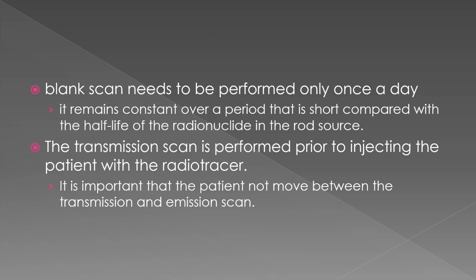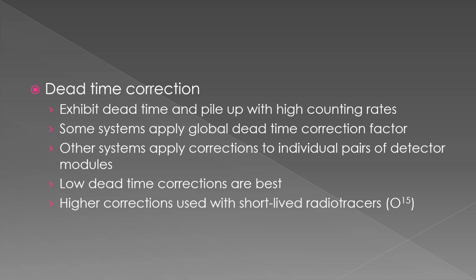Now, a blank scan is performed once a day. The blank scan is basically like our daily uniformity. It remains constant over time. You're testing the corrections and calibrations that you did and making sure that there aren't any non-uniformities or artifacts on the images.